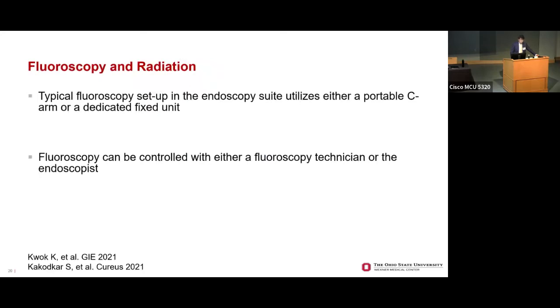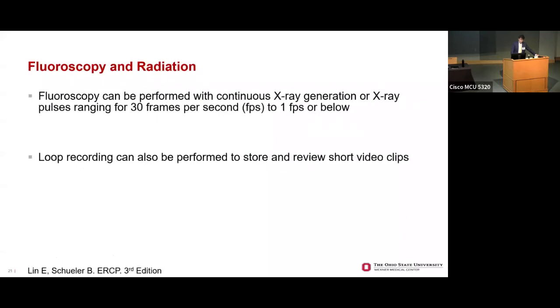Usually you see a portable C-arm most in the OR. And then they can be controlled with either a fluoroscopy technician or the endoscopist. I think my general preference and many endoscopists' preference is to be able to control their own fluoroscopy. And fluoroscopy can be performed with either continuous X-ray generation or pulsed X-rays, starting at a frame rate of about 30 frames per second to less than 1 frame per second. And then loop recording is a feature that's available in most units that basically allows you to store and review short video clips of fluoroscopy.